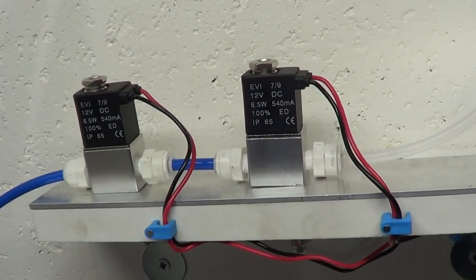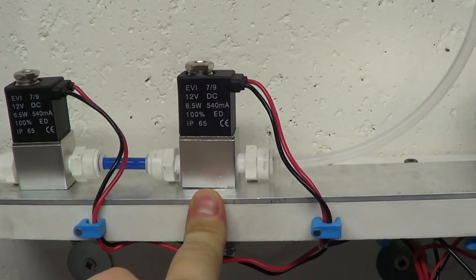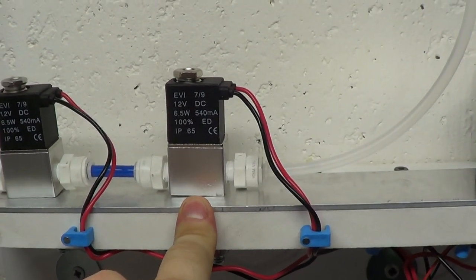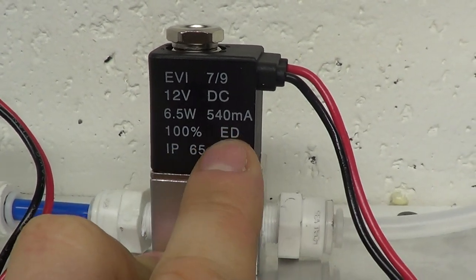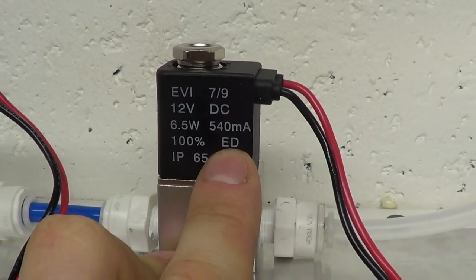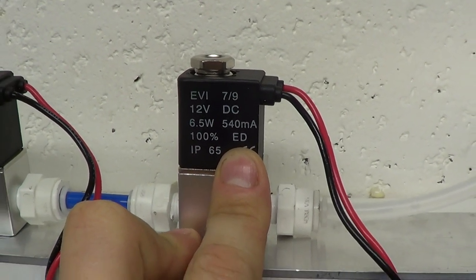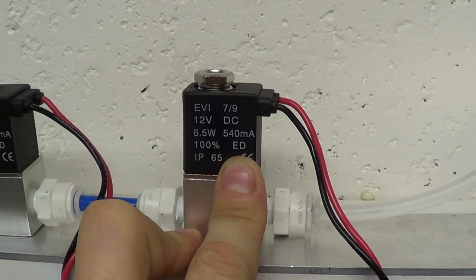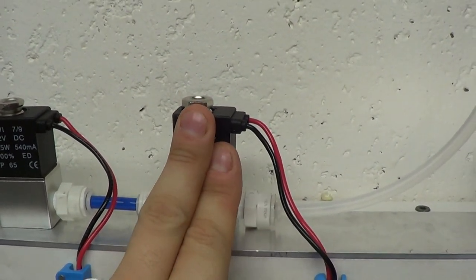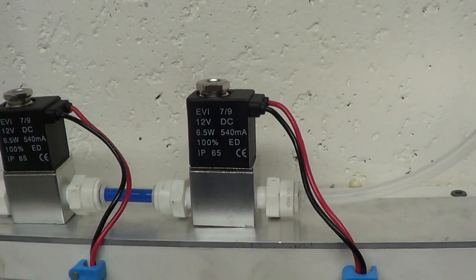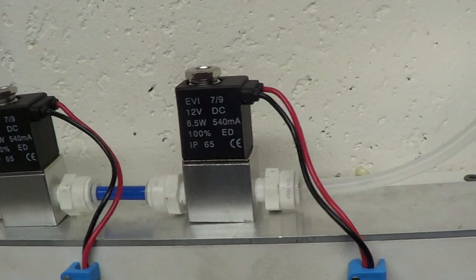Now, the most important thing when picking a solenoid valve, as I learned, is to find one that says 100% ED. And basically what that means is it's rated for continuous use. A lot of solenoid valves out there are not rated for continuous use, and what that means is this electromagnet will heat up to a very high temperature, actually to the point where your components could fail.